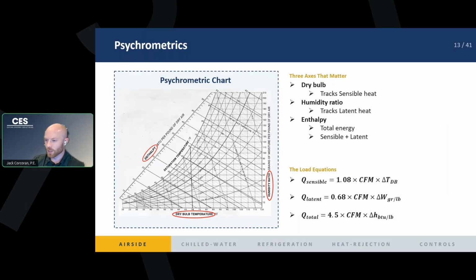Now, if you go to the vertical axis and you look at the humidity ratio, that's where the amount of moisture in your air is determined, right? And you can see that that's your latent cooling and heating, right? And so your air temperature, right? If you know what your air dry bulb temp is and you know what your air humidity ratio is, you can plot it on this chart and you can figure out the other properties such as your enthalpy, right? Or your relative humidity percentage. So this chart is pretty powerful. And if you know just two of the properties of your air, you can chart it on here and you can find out your other pieces of information.